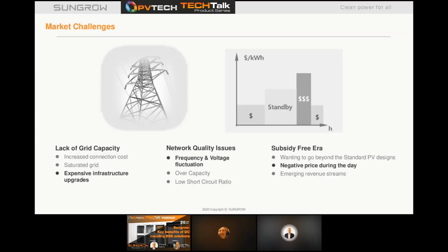As countries rapidly increase deployment of renewable technologies, this can have an adverse effect on the actual grid infrastructure, such as lack of grid capacity. The cost of reinforcement works can be astronomical and potentially render a project dead from the off. Network quality issues also arise - managing the grid with large amounts of aggregated microgeneration can present challenges, such as frequency and voltage fluctuation. Then there's the subsidy-free situation: what to do once feed-in tariffs or renewable subsidies drop or are withdrawn, and how do we navigate the next revenue opportunities? On the graph, we see periods where the system is in standby, potentially due to negative energy prices on the network.